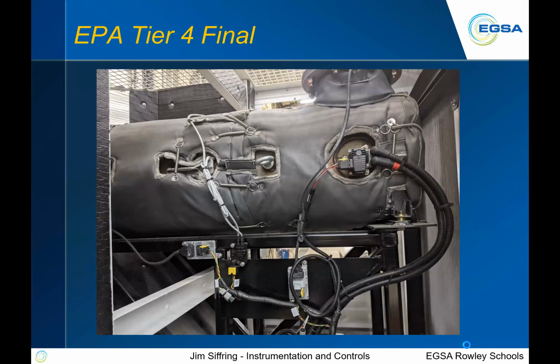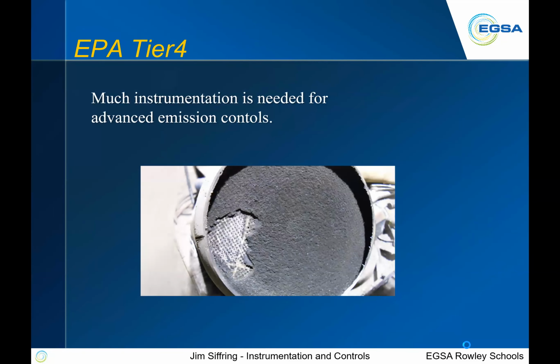And I sure wish my cursor was working, but I can point out, you see the two big hoses on the right-hand side goes into the DEF dosing unit. If you look at the bottom on where the metal frame meets the thermal wrap, you'll see a couple of devices. Those are the NOx sensors. Then we have a couple of temperature sensors in there as well. All those devices are right there. There's a whole lot of instrumentation needed to keep something like this happening.